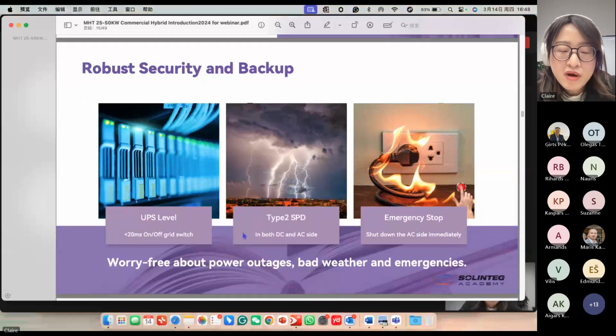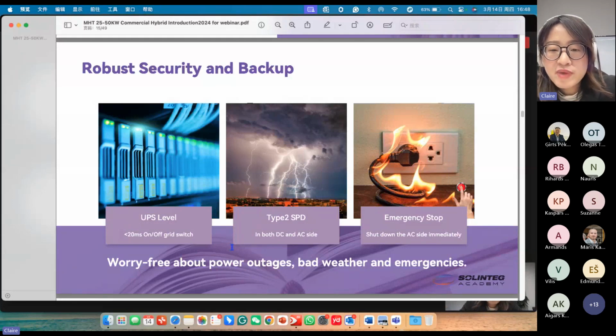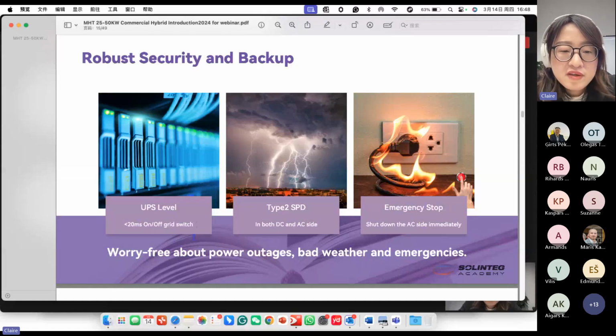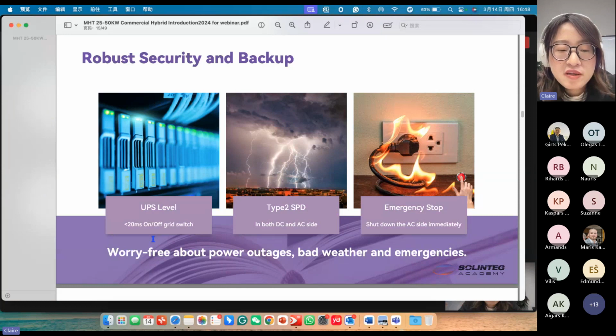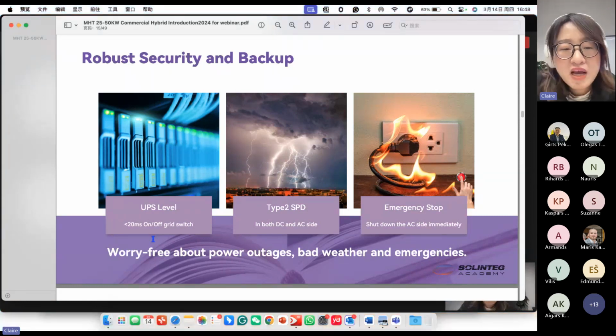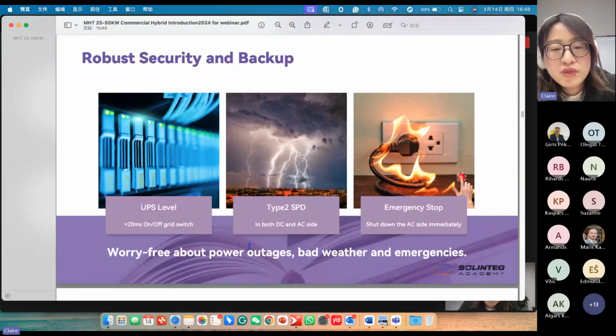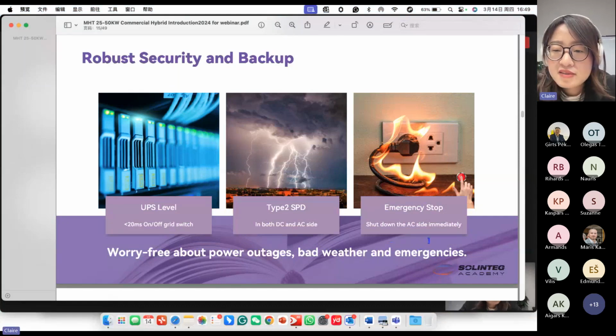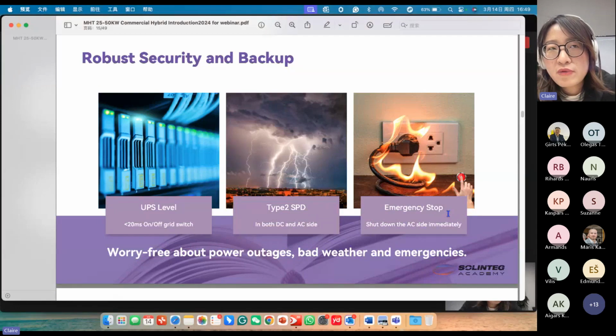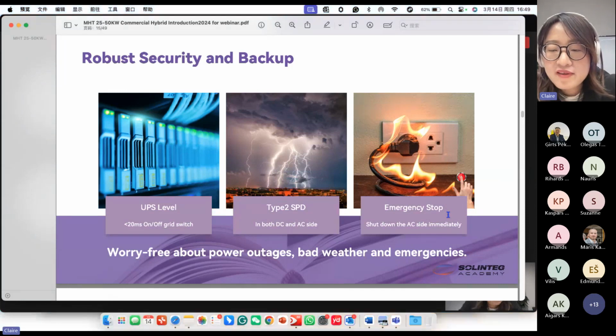And we also provide some protections for the customer from many different aspects. The first one is UPS-level switching over. If there are always power grid outage problems, the inverter supports less than 20 millisecond on-off switching. This enables the power to smoothly go to the backup side to support the critical loads when the power goes off. And we also integrate Type 2 surge protection on the DC and AC side. So this can avoid the inverter being damaged in lightning weather. And by connecting an external emergency button to our inverter, we can realize the emergency stop function. If an accident occurs at the inverter installation place, we can press a button to immediately stop the inverter AC power generation.